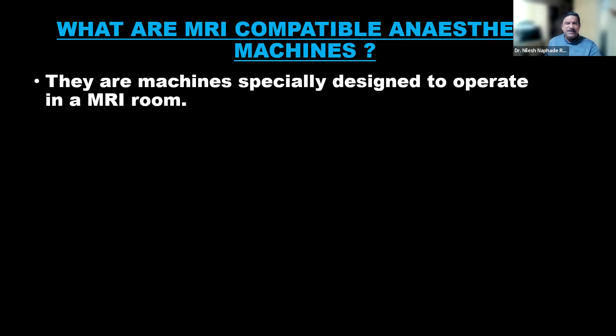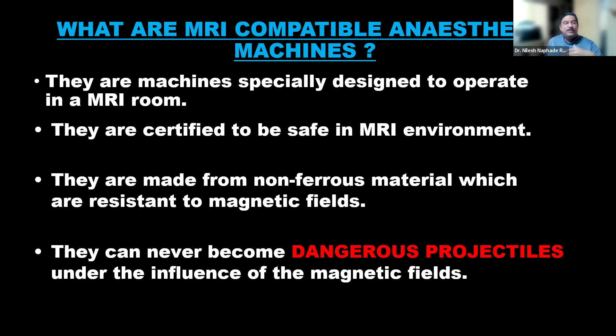Now comes the term MRI compatibility. What are MRI compatible anesthesia machines? They are machines specially designed to operate in an MRI room. They are certified to be safe in the MRI environment. They are made from non-ferrous material which is resistant to magnetic fields. There is a big list of non-ferrous metals, titanium and stainless steel and many more. They can never become dangerous projectiles under the influence of magnetic fields. What? MRI compatible anesthesia machines can never become dangerous projectiles under the influence of magnetic fields.